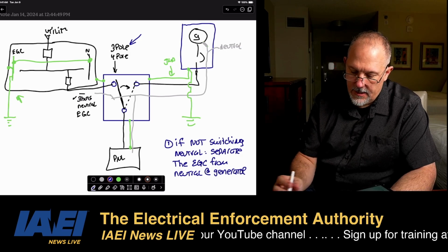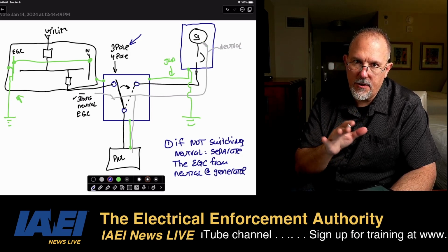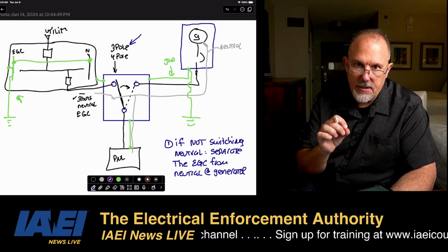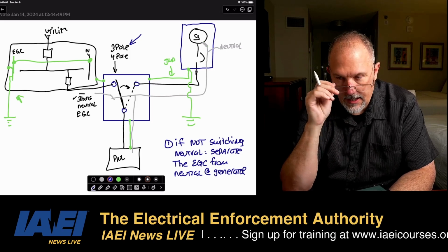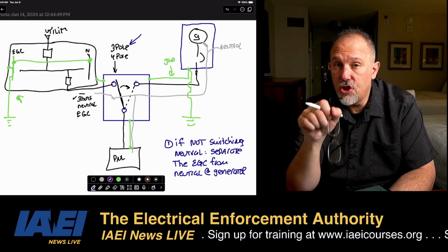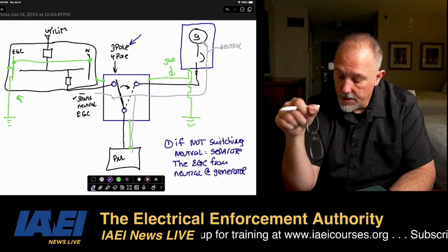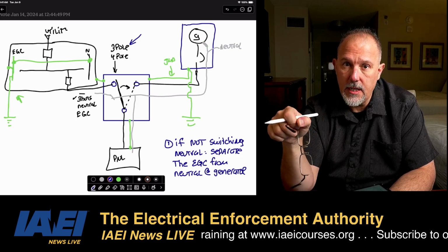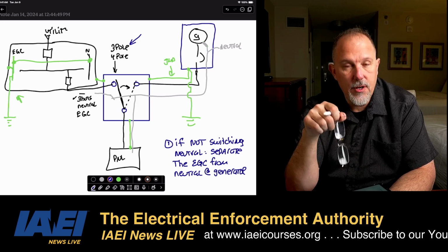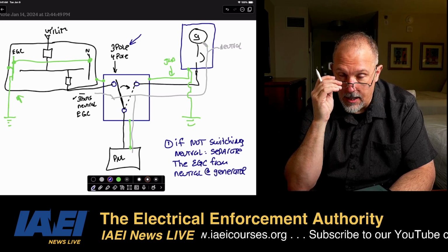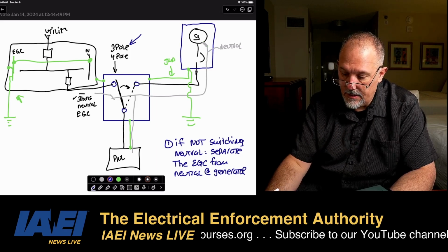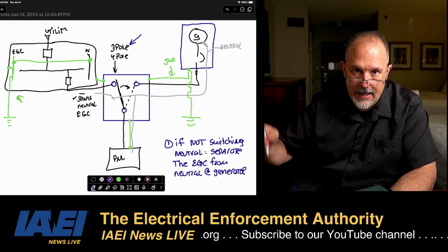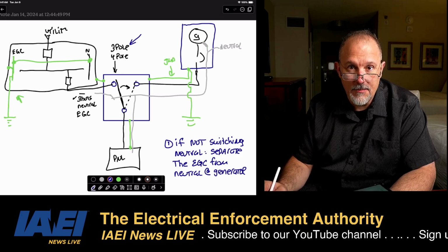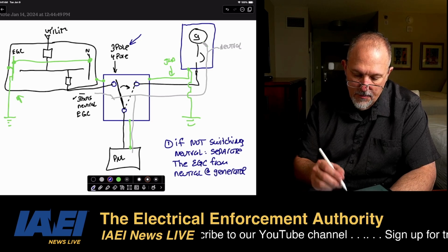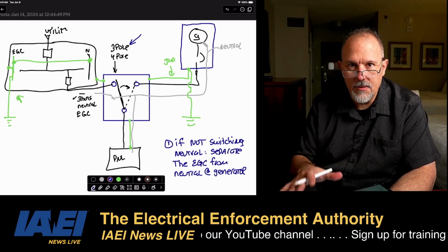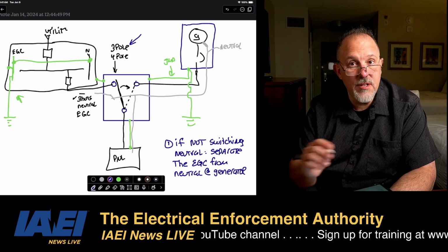Now, why is that? Some generators may ship bonded, and you have to take a look in the generator and look at the instructions that come with the generator to determine whether or not there is a bonding going on. And if you have a 3-pole transfer switch and it's bonded and you drove a rod, for whatever reason, there's no code requirement that says you have to drive a rod at that generator if it's a non-separately derived system. You have a 3-pole transfer switch, that generator is a non-separately derived system because the neutral is common.